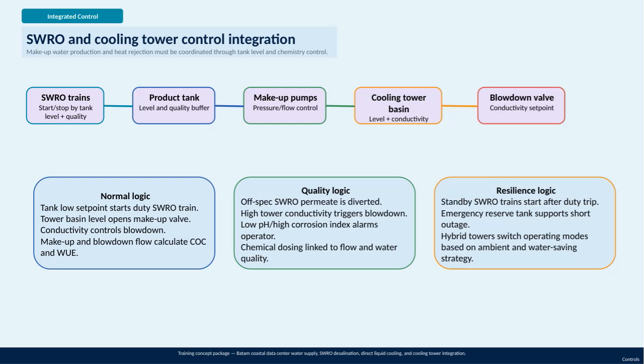This slide focuses on the integrated control system for the Batam Coastal Data Center's water supply, combining SWRO desalination and cooling tower operations. The key is coordinating makeup water production and heat rejection through precise tank level and water chemistry control. Starting with the SWRO trains, they operate based on tank level and water quality, automatically starting or stopping as needed. The product tank functions as both a level and quality buffer, ensuring consistent supply. Makeup pumps regulate pressure and flow to maintain system stability, while the cooling tower basin monitors level and conductivity to optimize performance. The blowdown valve is controlled by conductivity set points to manage water quality within the cooling tower.